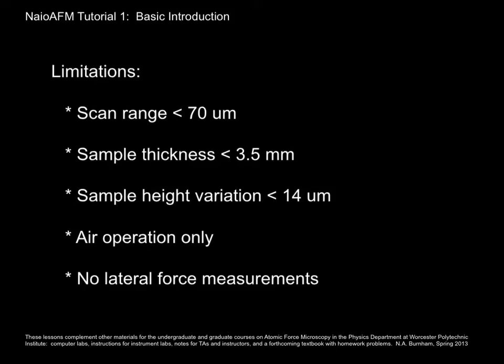Before we go much further, I'd like to tell you about what the NaioAFM does not do. It does not scan larger than 70 microns. It does not take samples thicker than 3.5 millimeters. If the sample height variation is greater than 14 microns, we won't be able to track it. It only works in air and does not do lateral force measurements.